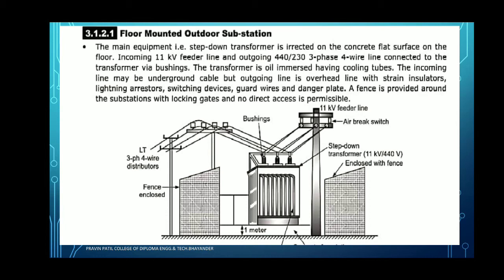The main equipment of this substation is the step down transformer, that is the main component of the floor mounted outdoor substation. That step down transformer is erected on the concrete flat surface as shown in this diagram. On that surface the step down transformer is mounted, and the distance between the floor and the transformer is about 1 meter. The incoming 11 kV feeder line and outgoing 440 volt or 230 volt 3-phase 4-wire line are connected to the transformer via bushing. That bushing is connected to the incoming and outgoing points.